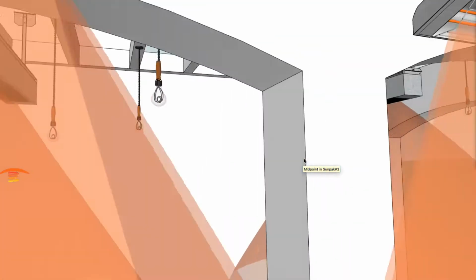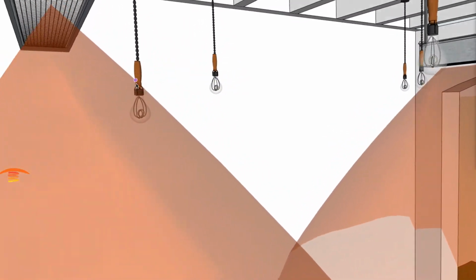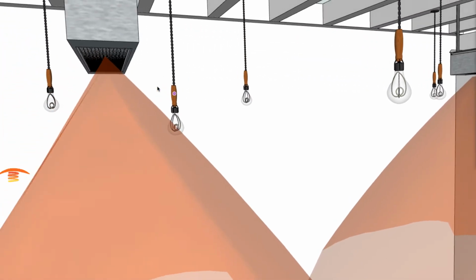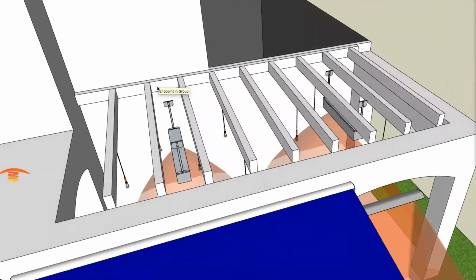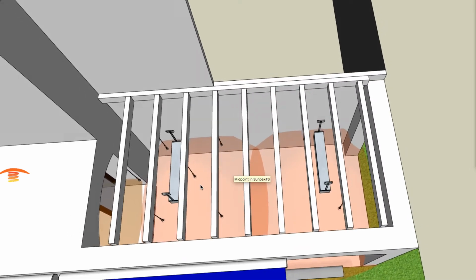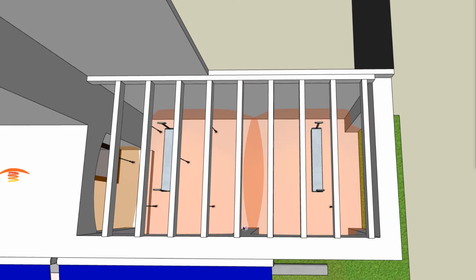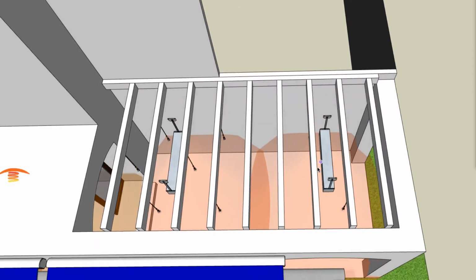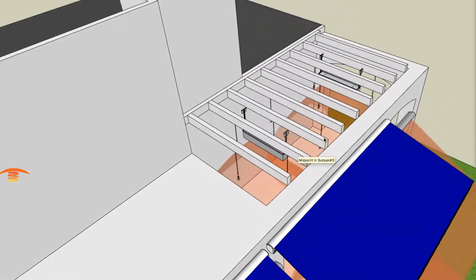That'll be the major concern: if we place the lamp inside of the ray. This one's physically not in it, but if it was, then we'd want to move that lamp over to accommodate the heater's placement. But if you can see here, you have a nice even coverage within the space. You have a little bit of overlapping, which is about a foot, foot and a half of overlapping at that 9 foot elevation height. And that'd be perfect for this space that they want to utilize.